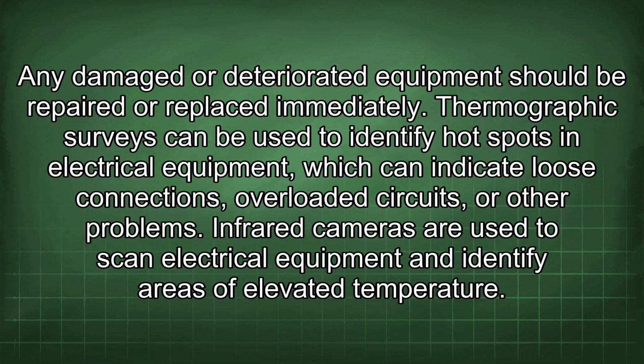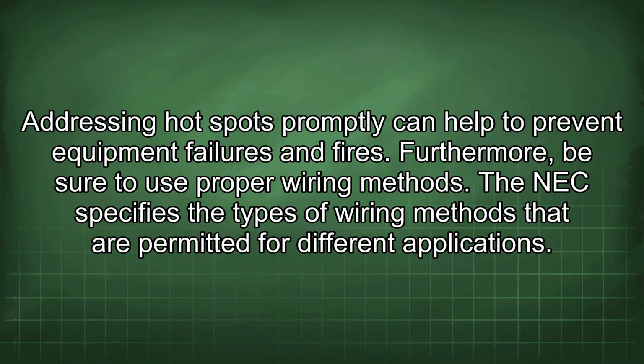Thermographic surveys can be used to identify hotspots in electrical equipment, which can indicate loose connections, overloaded circuits, or other problems. Infrared cameras are used to scan electrical equipment and identify areas of elevated temperature. Addressing hotspots promptly can help to prevent equipment failures and fires.